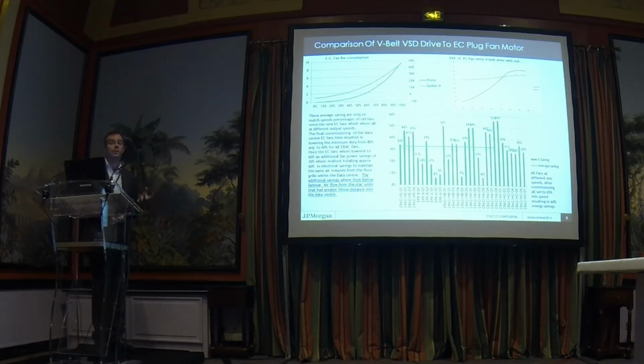The efficiency where this comes in is where the air isn't being turned anymore, it's being thrown directly straight out. The air just travels sideways out of the machine, straight to where it needs to do its work. So all these different numbers here is where all the different air conditioners were at different stages on their return air control philosophy at the time. So some were running at 40%, some were running at 80%, so that's why you've got these really great big percentages of savings here.